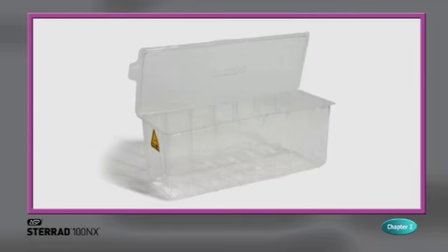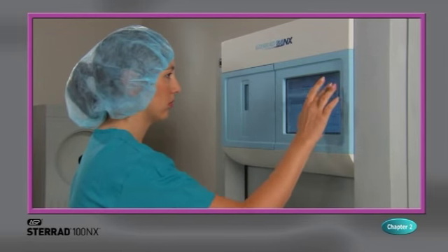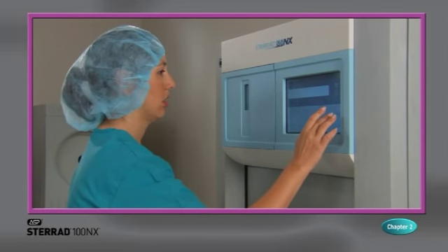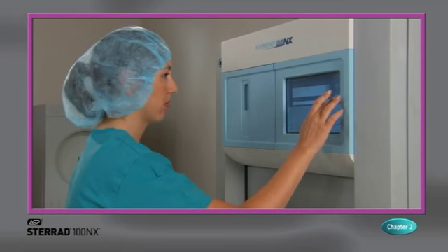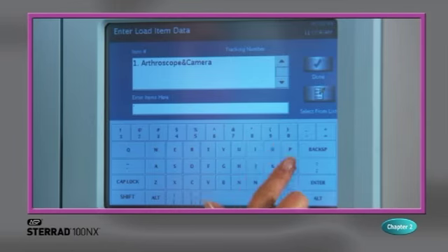The sterilizer displays information and allows you to enter commands on the color touchscreen display. By touching buttons displayed on the screen, you can enter letters and numbers, make selections, and start and stop the sterilizer. An internal loudspeaker emits beep tones to call for user attention or indicate errors. A single long beep indicates a successfully completed cycle. A series of 10 short beeps indicates a canceled cycle.